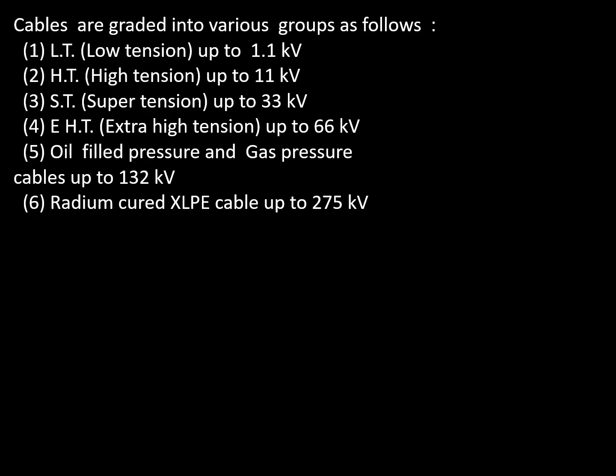According to voltage rating, the cables are grouped in various portions. First one is LT, or so to say MV, medium voltage, up to 1.1 kV. Then HT, high voltage, HV system up to 11 kV, ST super tension up to 33 kV, EHT extra high tension up to 66 kV, and oil filled and gas pressure filled up to 132 kV, and radiation cured XLP cable up to 275 kV. So this is the cable classification in increasing order of voltage.